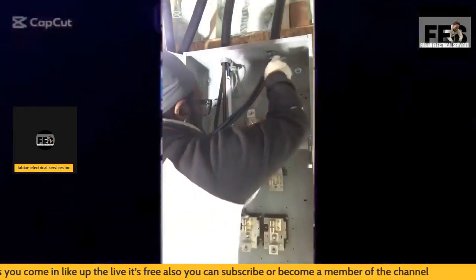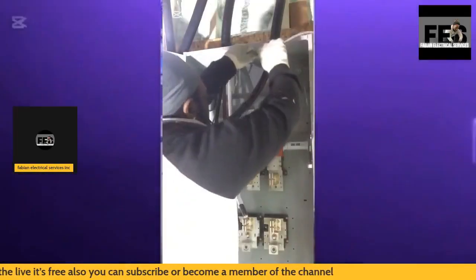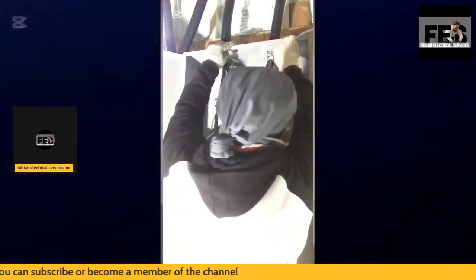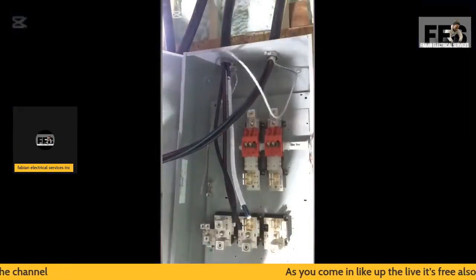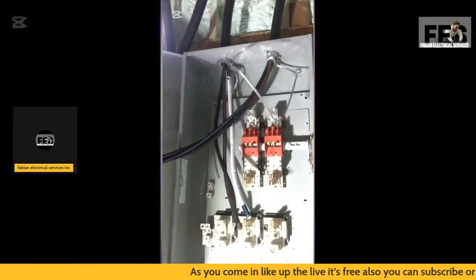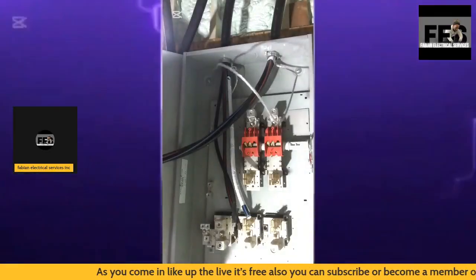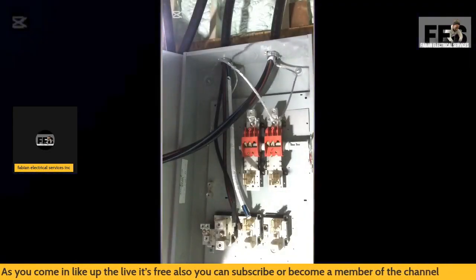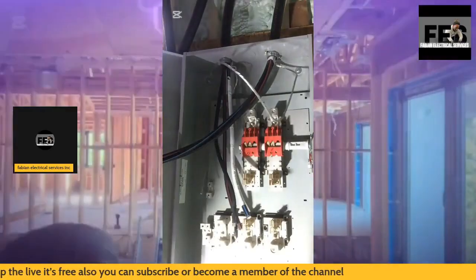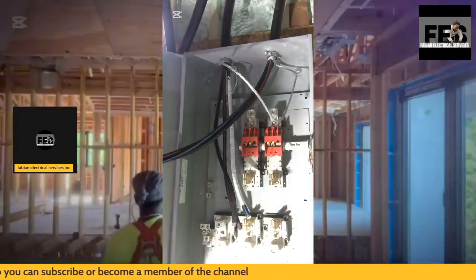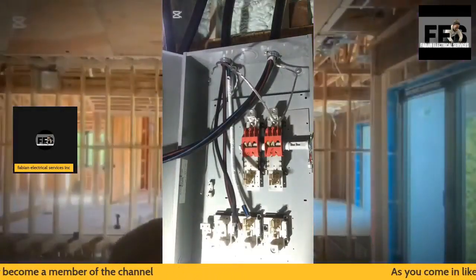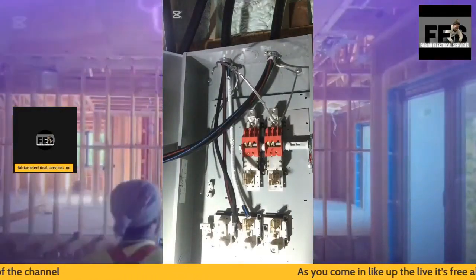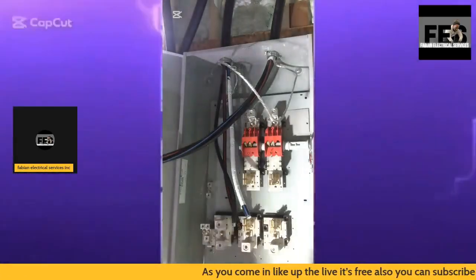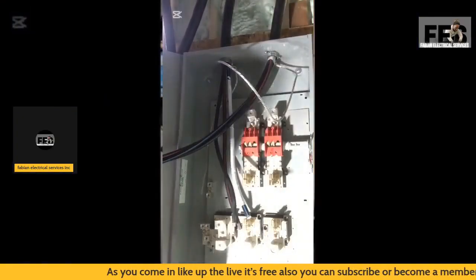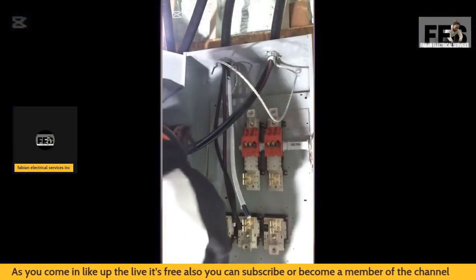Also, you're going to see I have my phasing tape on my cable. The reason is this cable does not come with an identified neutral, and in the code book it states that your incoming neutral has to be identified. There is an electrical code rule that states that a particular size of cable must be identified, so this is what I am doing here, identifying my conductors with the white tape that is being used.